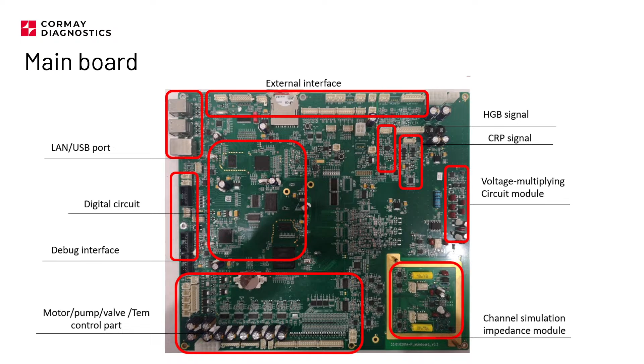This analyzer is actually using high voltage pulses to clean the aperture. Any debris which can potentially be stuck in the aperture or counting head area will be destroyed or burned by the high voltage pulses. Right before each analysis, actually, there is a few second burst of high voltage just to remove this from the circuit.